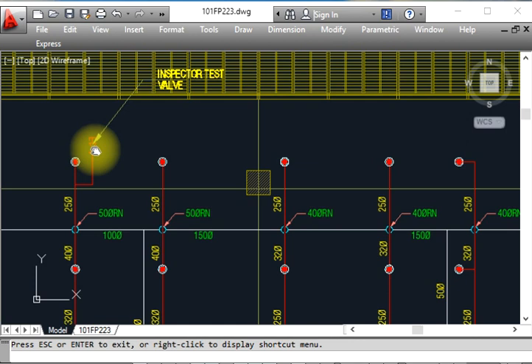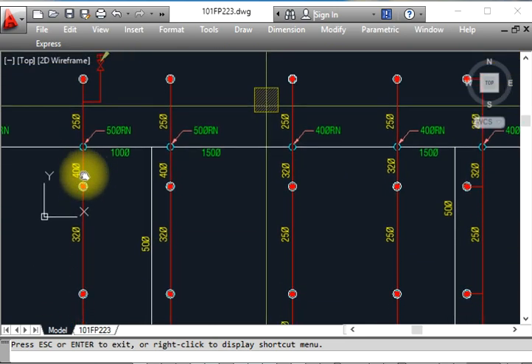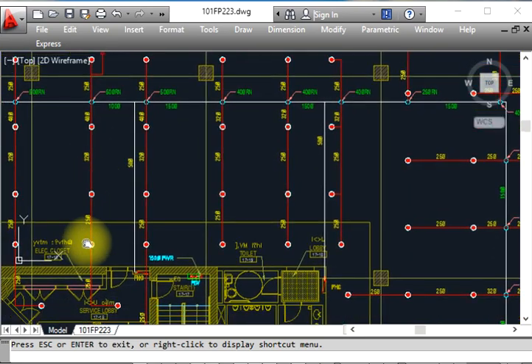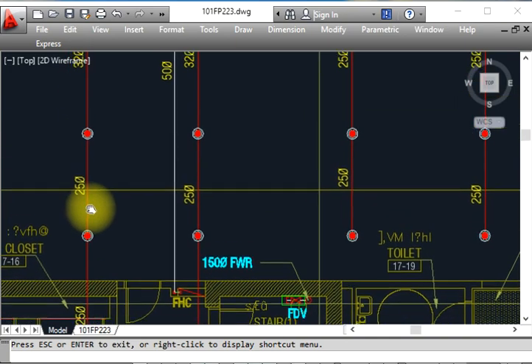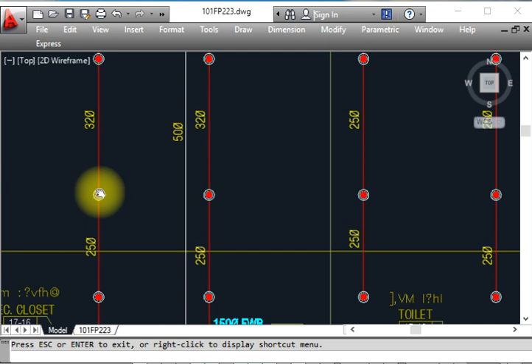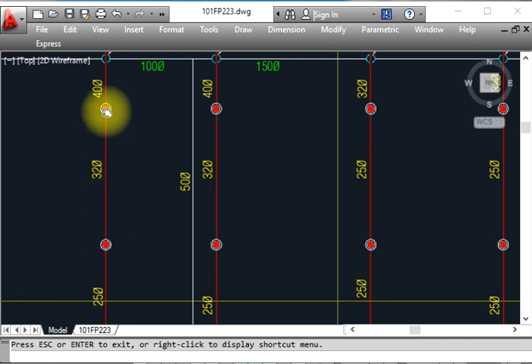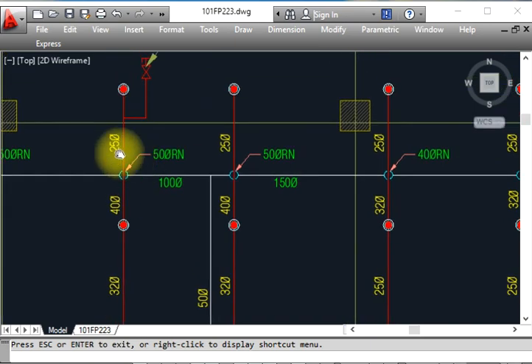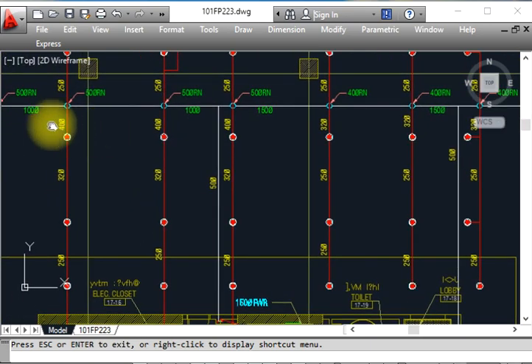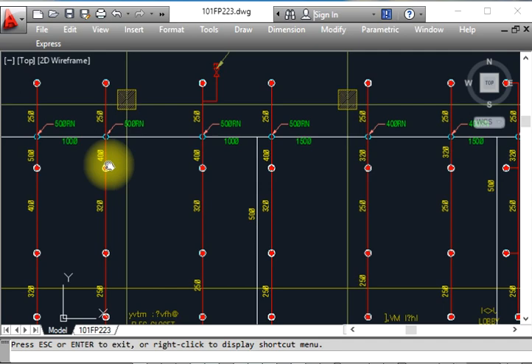If the gauge still shows 12 bar it means it's okay. If the pressure has dropped a little bit, there is some leakage somewhere — we reject it and redo the work. For example, in the service lobby: 25mm, two sprinklers at 25mm, three sprinklers, and then 32mm. The 32mm will contain only one sprinkler, after which it becomes 40mm. Only one sprinkler going here with 25mm, so distributing at 40, 32, 25, 25.